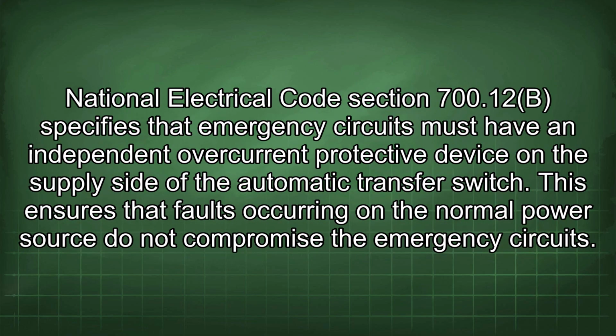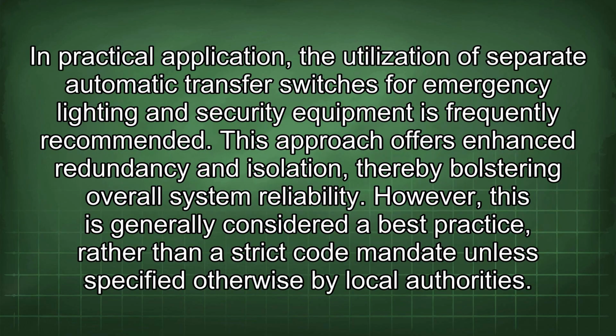National Electrical Code Section 700.12b specifies that emergency circuits must have an independent overcurrent protective device on the supply side of the automatic transfer switch. This ensures that faults occurring on the normal power source do not compromise the emergency circuits. In practical application, the utilization of separate automatic transfer switches for emergency lighting and security equipment is frequently recommended. This approach offers enhanced redundancy and isolation, thereby bolstering overall system reliability. However, this is generally considered a best practice, rather than a strict code mandate unless specified otherwise by local authorities.